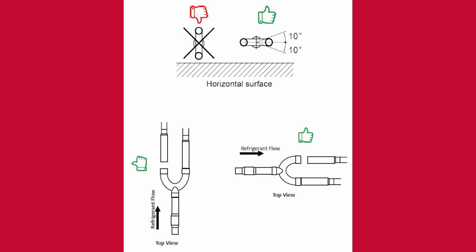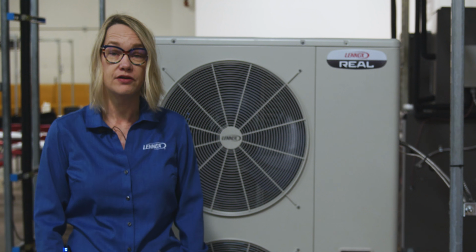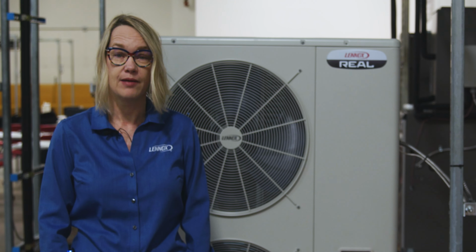The REAL system has one continuous pipe run using a branch joint to branch off to the second indoor unit. If the branch joint is installed on a horizontal piping run, it must be installed level, plus or minus 10 degrees. If the branch is installed on a rise, it must be installed straight up or down. Refer to the REAL outdoor unit installation manual for additional piping information.